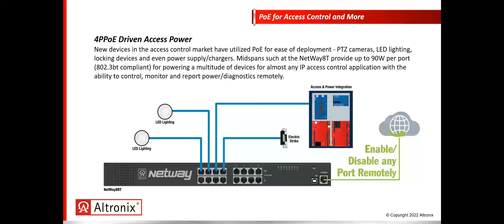The future of access control, the Tango 1B, is a 4P PoE driven power supply. So 4 pairs, you have your Cat 6A coming in. Typically we like to use Cat 6A because there's less heat dissipation in the line and less loss of power. At 100 meters, you can get 72 watts available out of your power supply to your device. So 90 watts comes from the power sourcing equipment, and you have about an 18 watt loss because the device will consume up to 72 watts.